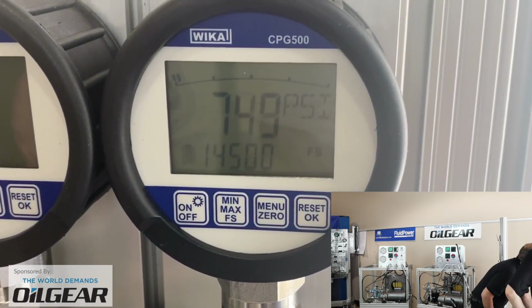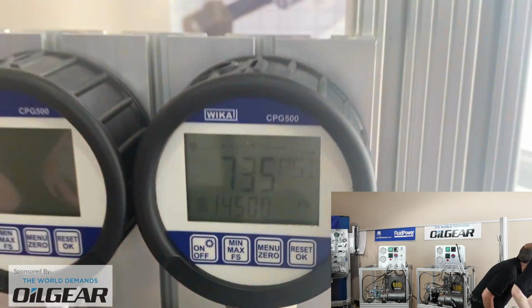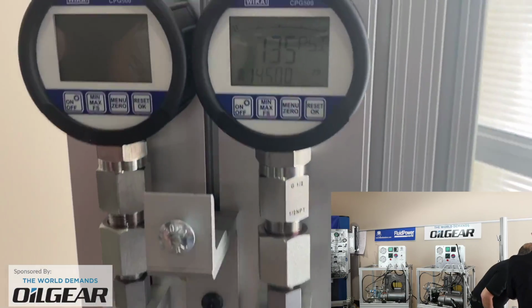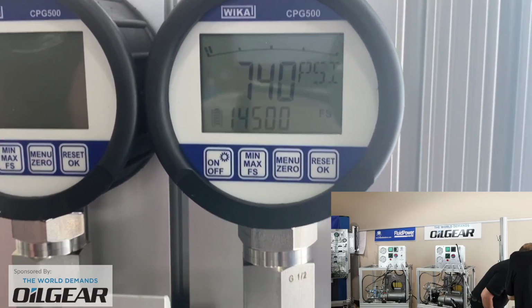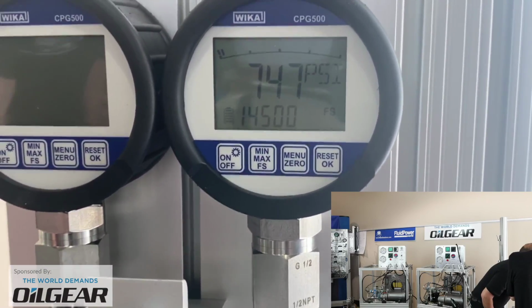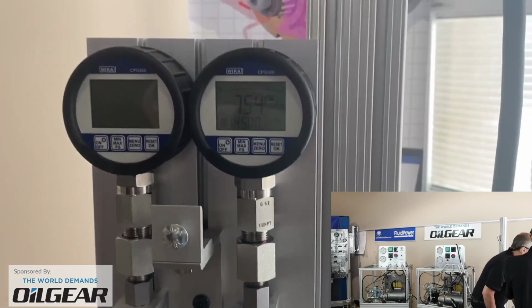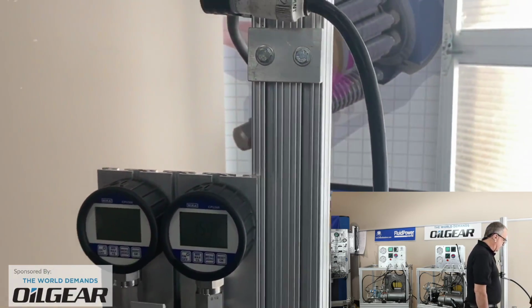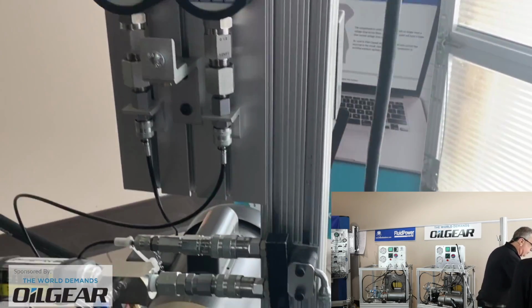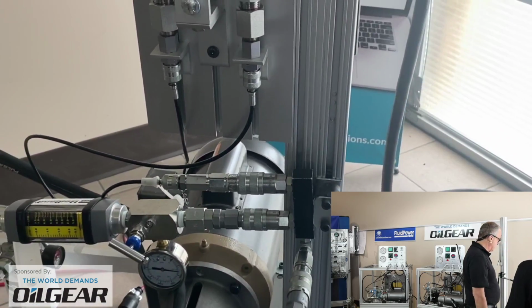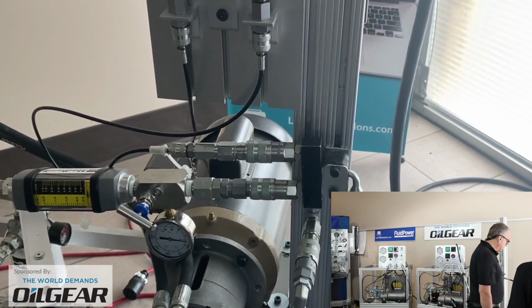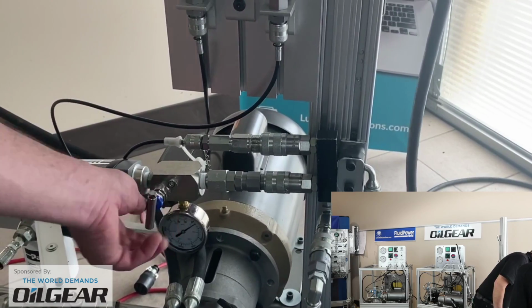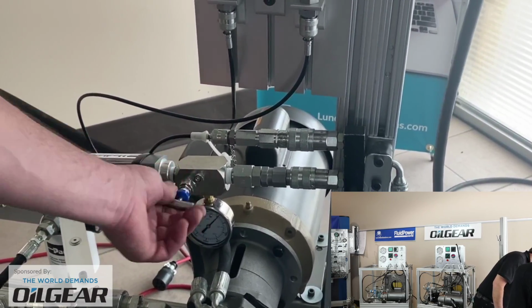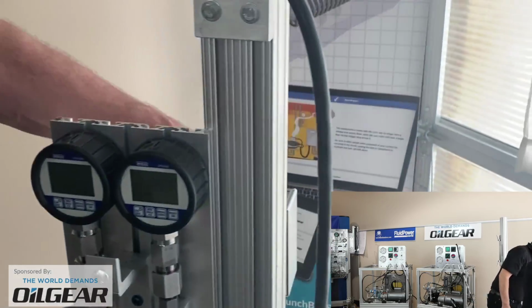I'll come back down, go underneath a little bit, and give it very small turns. It was about a third of a turn to go from 500 to 750 on the pressure compensate, and it's not all that complicated. Our pressure compensator has been set, and again the assumption is that you have a relief valve in the system that has already been adjusted. Okay, so that's one example.